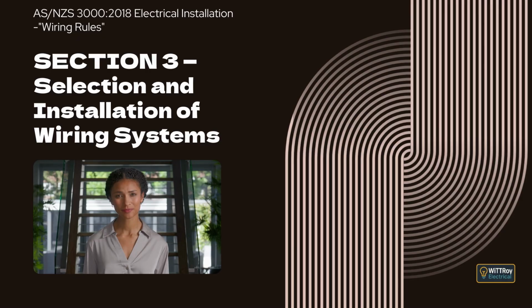Clause 3.9, Installation requirements. This clause sets out how wiring systems must be installed so they remain safe, reliable, and fit for service over their full life, taking into account normal use, foreseeable misuse, wear and environmental conditions. Clause 3.9.1, General. This clause explains that wiring systems must be installed using accepted good electrical practice. The methods used must protect the installation against mechanical damage, electrical failure, deterioration from normal wear, and abnormal conditions that can reasonably be expected. The overall intent is that the installation remains electrically sound and mechanically secure in everyday service.